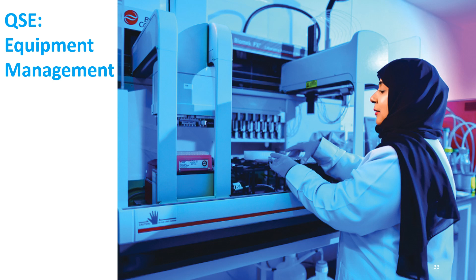The first quality system essential is equipment and its management. We need to take care of various aspects such as installation. Before the installation, we should put in the specification of the machine, then send it to procurement. After that, we receive the machine. We need installation by the manufacturer or the supplier, validation, maintenance, calibration, troubleshooting by the staff, repair and maintenance, and a service report if anything happens to the machine, and records for everything, like checklists and records for troubleshooting, actions, or accidents that happen with the machine.